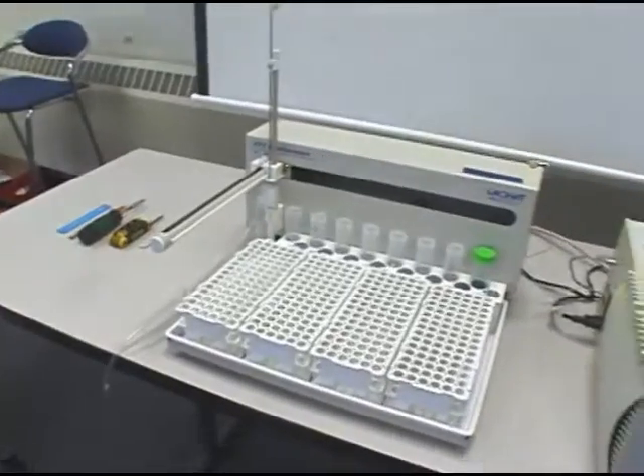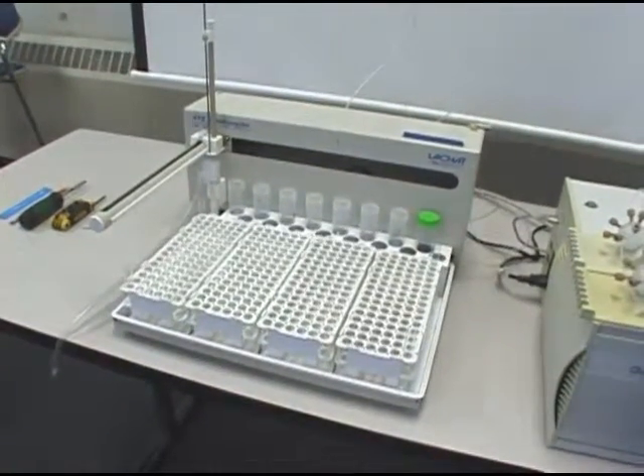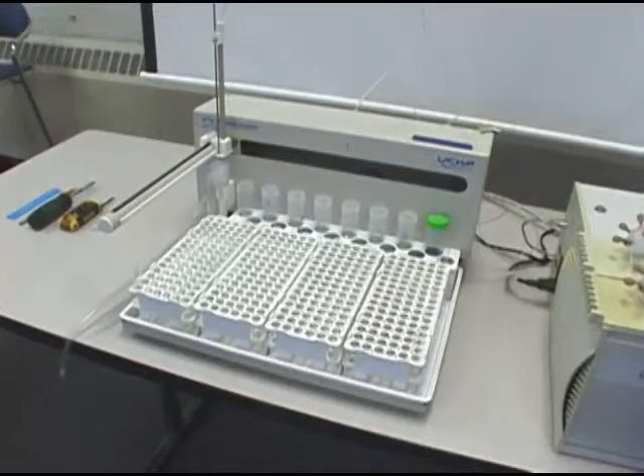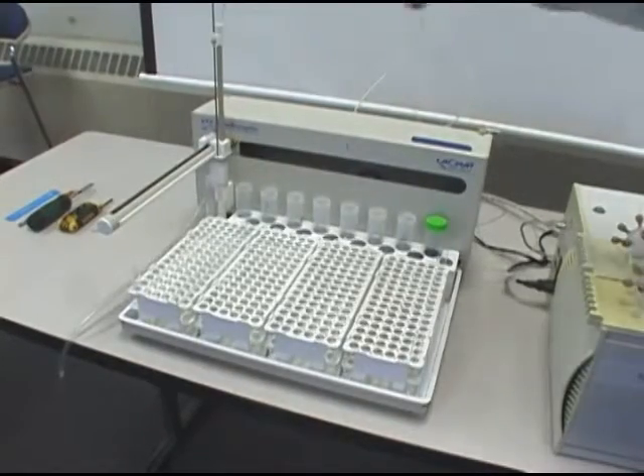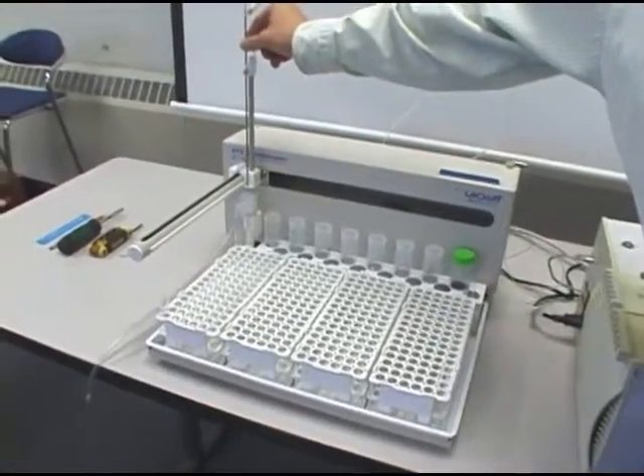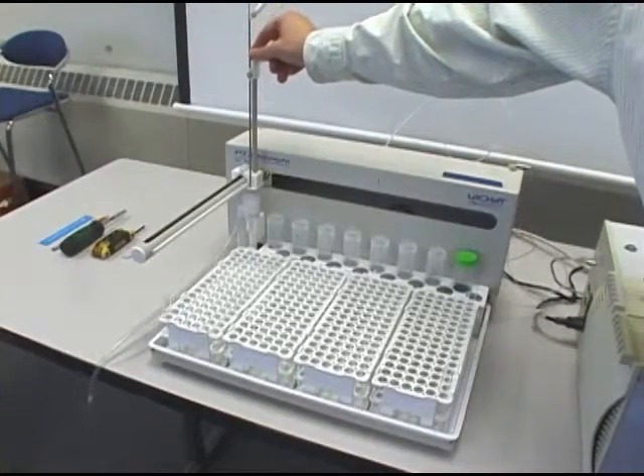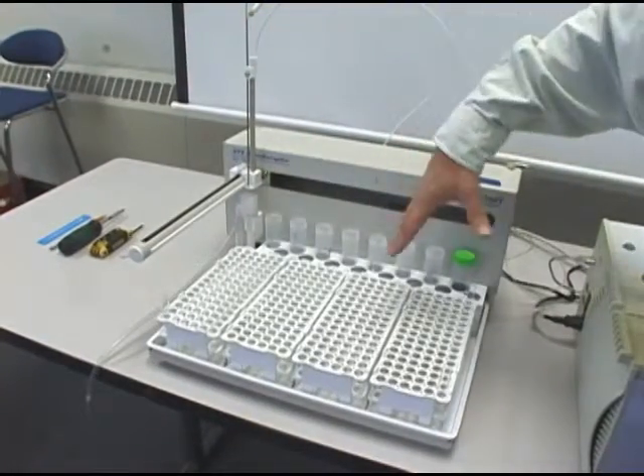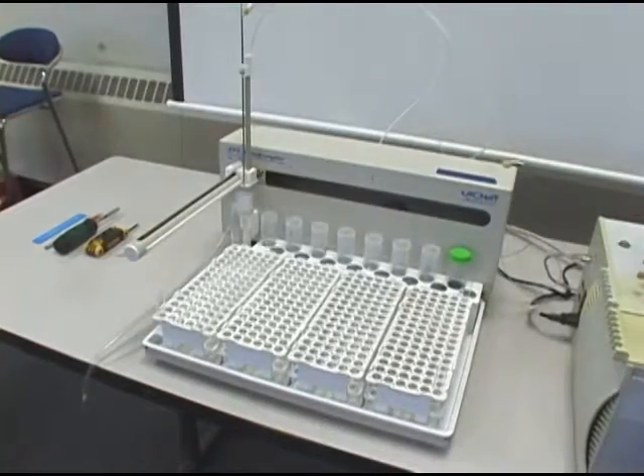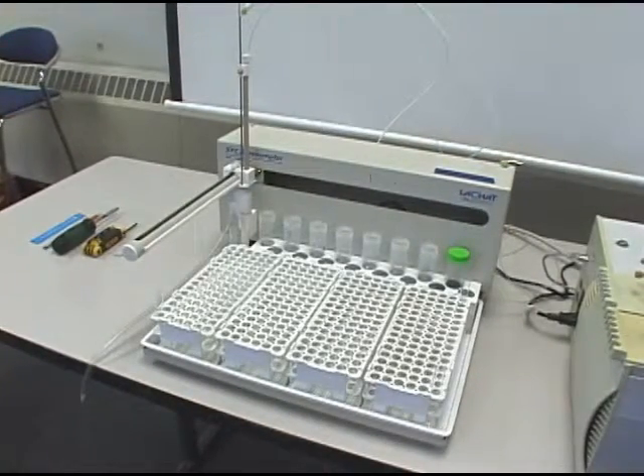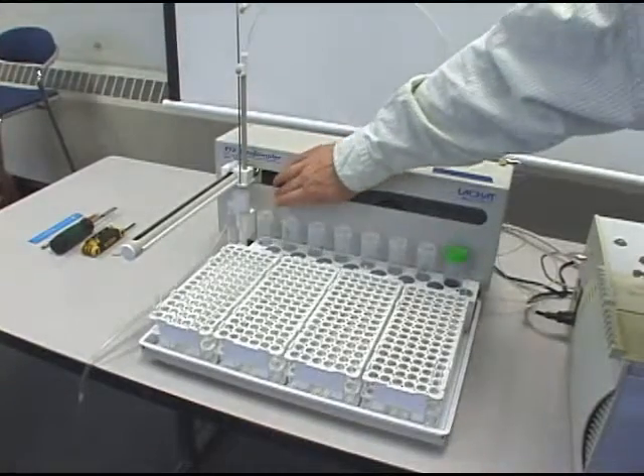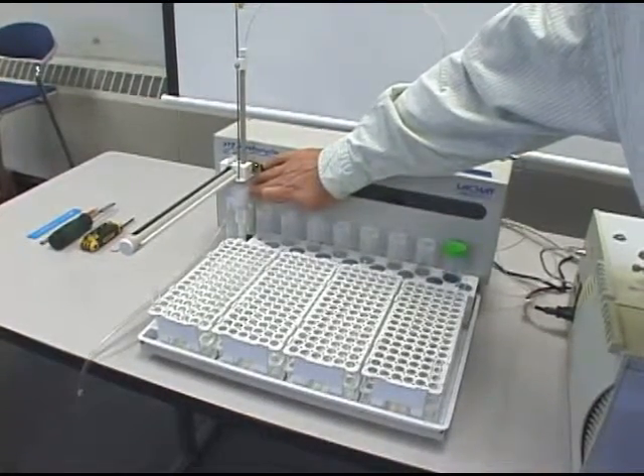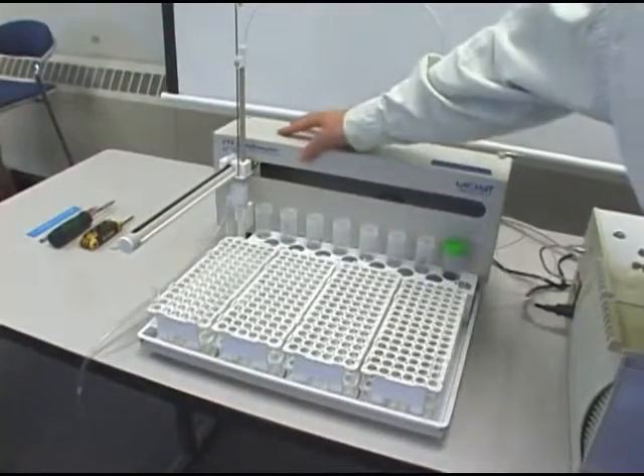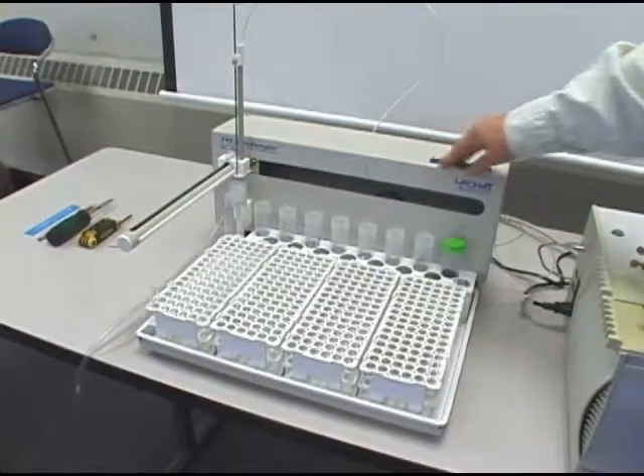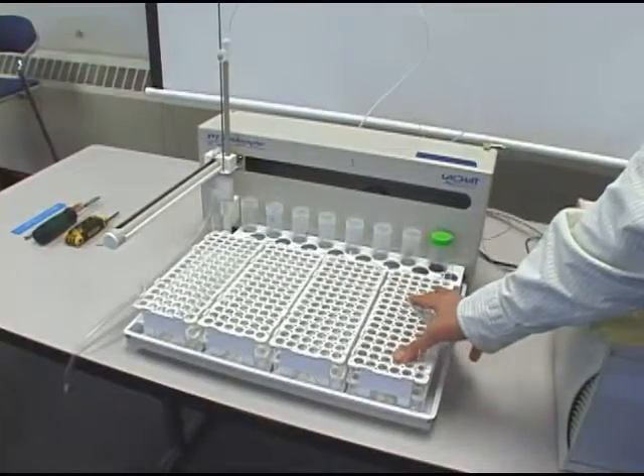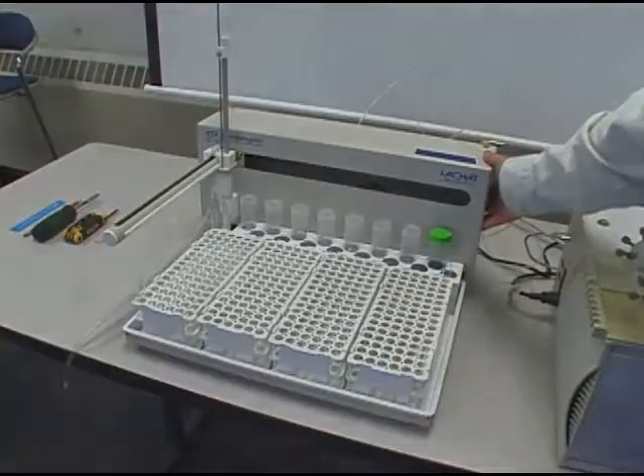Now, for realigning the auto sampler, it's basically a three-part process. The first part we're going to look at is straightening the sample probe. This can sometimes get bent, and sometimes that's all that's really needed to get the auto sampler back into alignment. The other two parts of aligning the auto sampler are to realign the wash bath on the base of the auto sampler, and also then realigning the tray of the auto sampler to the base of the auto sampler.